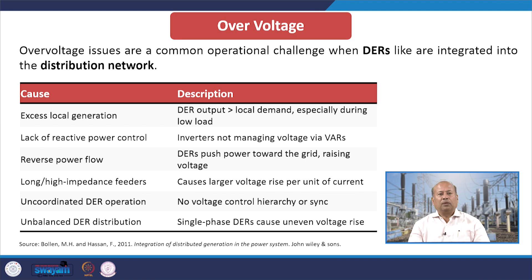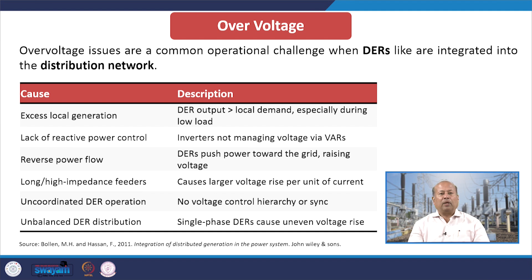Moving to over voltage: over voltage issues are a common operational challenge when DERs are integrated into the distribution network. The causes include excess local generation where DER output is much more than local demand especially during low load conditions, lack of reactive power control due to inverters not managing voltage via VARs, reverse power flow where DERs push power towards the grid raising voltage, and long high impedance feeders causing larger voltage rise per unit of current. Uncoordinated DER operation with no voltage control hierarchy or synchronization is also a cause.